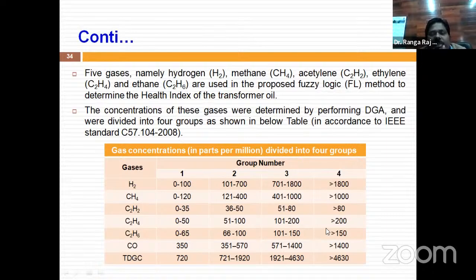Similarly for the other gases—for a good or excellent oil, all the values for all the gases are present in the first mode, excellent mode. For a moderate transformer, if all values are present in the second range, we can say it is good or moderate. If it is in the third range, poor; fourth range, worst. So in 4 cases, we can confidently tell the health status of the oil.